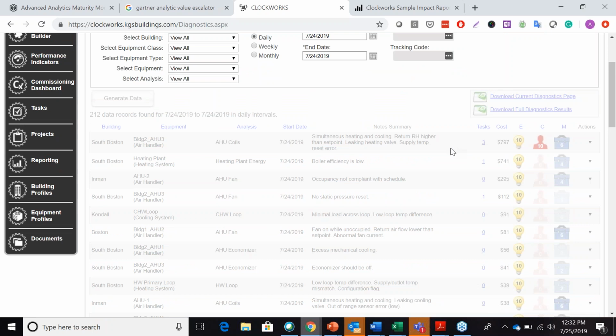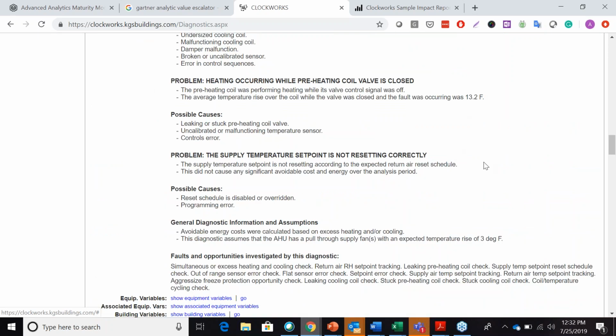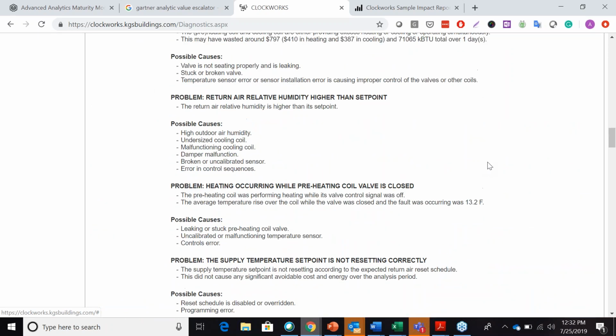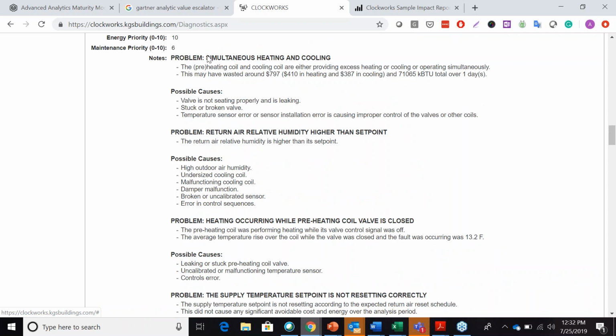So I'm going to go ahead and do that now. And we can see that each of those problems identified has a list of possible causes. So this plain English output here is automatically generated, and it's to really save time. So we have a lot of maintenance leaders that will tell us that, even if I have a guy with 25 years experience on my team, having that list of possible causes does save us a lot of time. So there's a dollar value here calculated from the heating side and the cooling side. And why is this issue happening? Well, the valve might not be seating properly and is leaking.